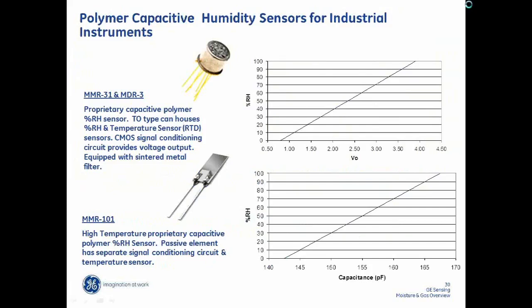Well, the next technology is our polymer sensors, and we have two types: a high temperature one, and the other is sort of a mid-range temperature. It goes up to 85 degrees C, and the one on the bottom goes up to 150 degrees C. The one on the top has an integrated CMOS circuit, which provides a voltage output, and the one on the bottom is a capacitance change. And these are somewhat similar to aluminum oxide, but rather than the aluminum oxide substrate, it's a proprietary polymer.